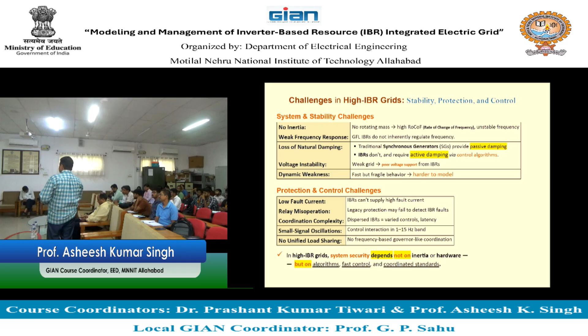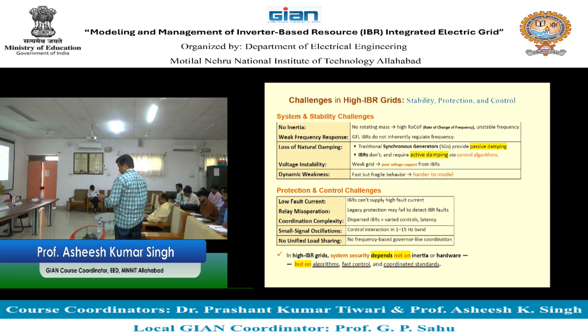In high IBR grids, system security depends not on inertia, because it is not present, or on any hardware, but it depends on algorithms, faster control, and coordinated standards. They control and they try to maintain our grid reliably for reliable operation. So why is GFM the way forward? Traditional IBRs assume a strong grid for synchronization and fault support. In high IBR or weak grid systems, the definition is here.